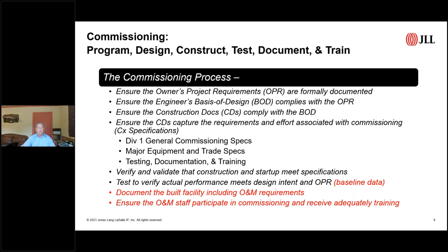That includes a Division 1 general commissioning spec, often written by the commissioning provider. It also includes making sure the major trade and equipment specifications have the commissioning requirements built in, such as whether equipment will be tested with load banks, who provides fuel for the generators, and who has to participate in the various testing.